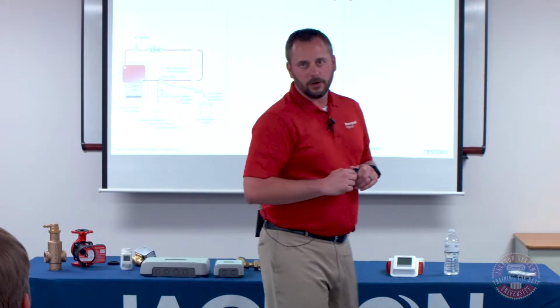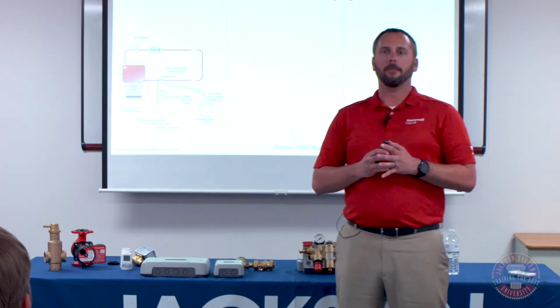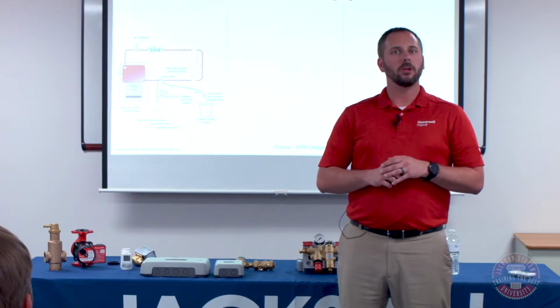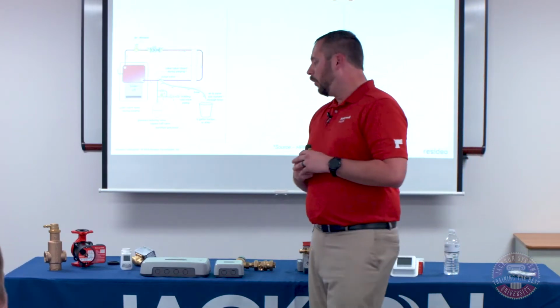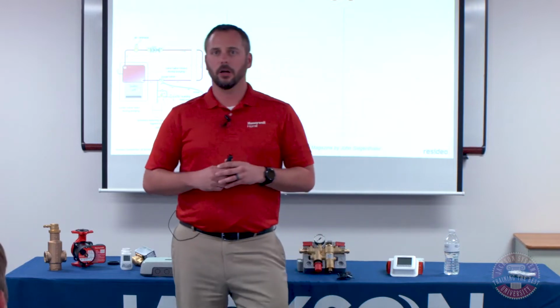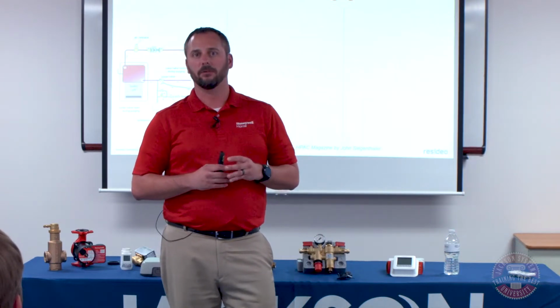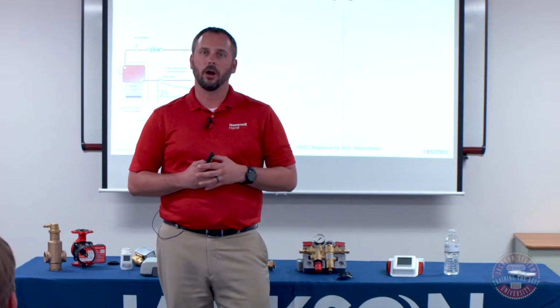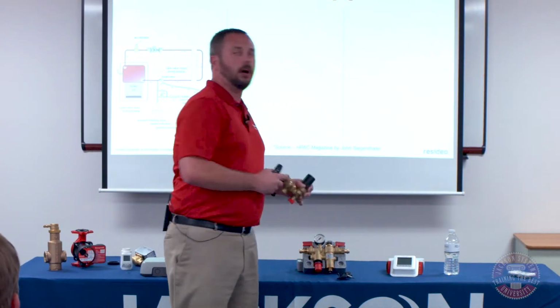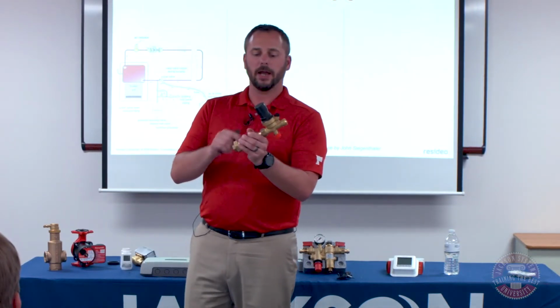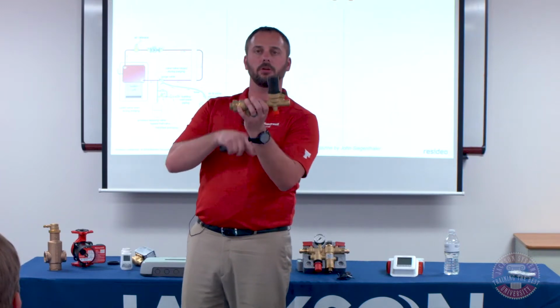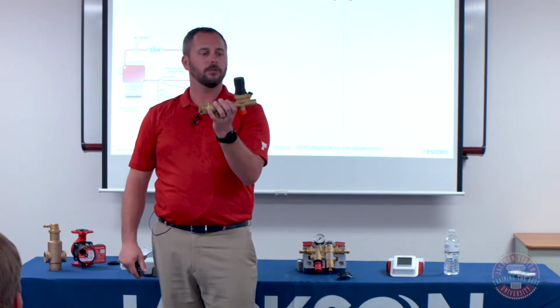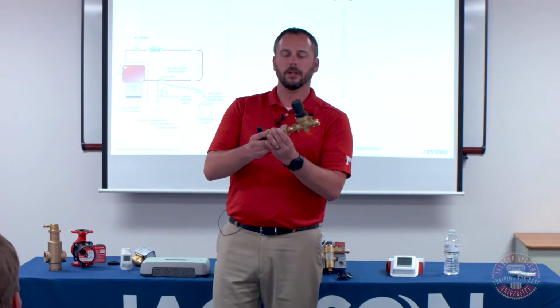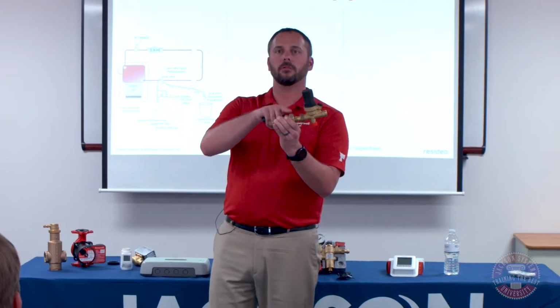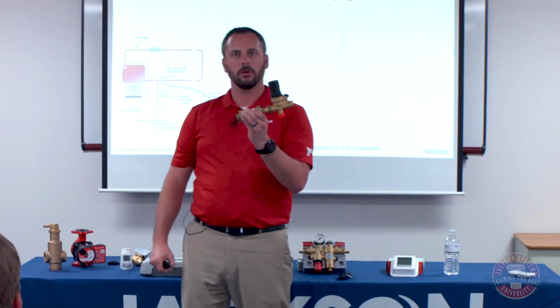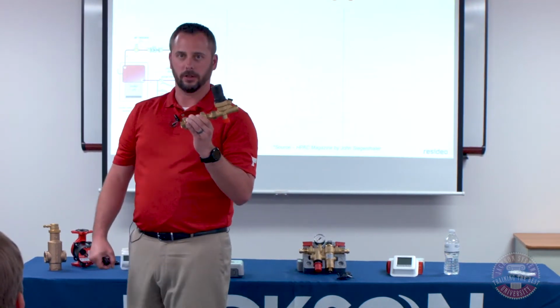So I talked on those two different devices. There are applications where you may want to use one or the other. One of the things that we see is certain areas of the country require RPZ testable backflow preventers. We don't have that in our current offering, but we do sell our fill valves separately. So I can take this backflow preventer apart, and you can basically marry that up to this. That'll give you your system. The other thing that I see some people like to do is create a manual bypass with a ball valve so that you can purge incredibly quickly.